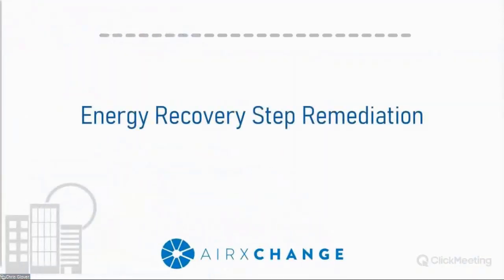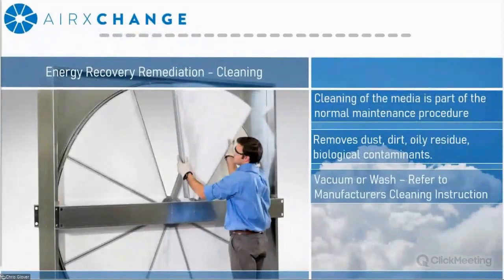Okay, so inspection evaluation once again may lead to potential remediation depending upon the condition of the system. Typical remediation for energy recovery systems is usually cleaning. I'd also like to mention that cleaning the media isn't just a pandemic related task. I know maintenance is often hard to get on particular units, but it really should be part of the normal maintenance and operation of these devices.